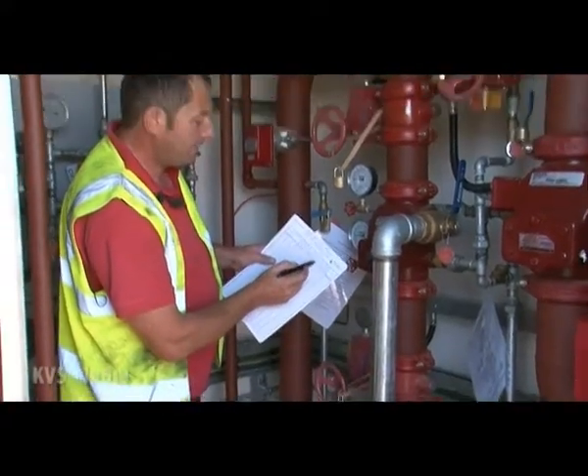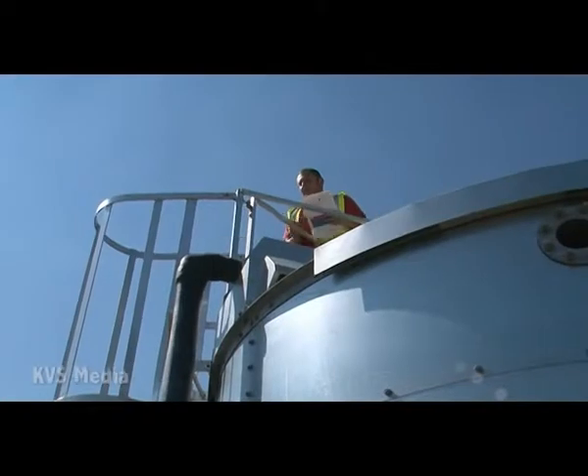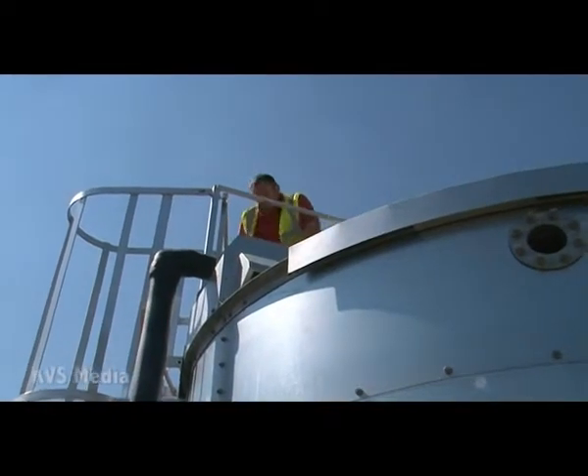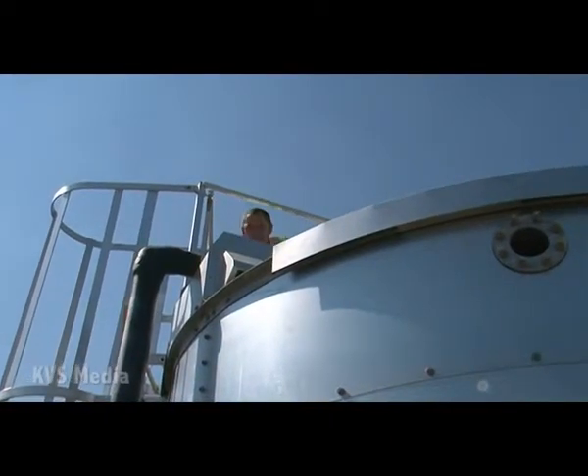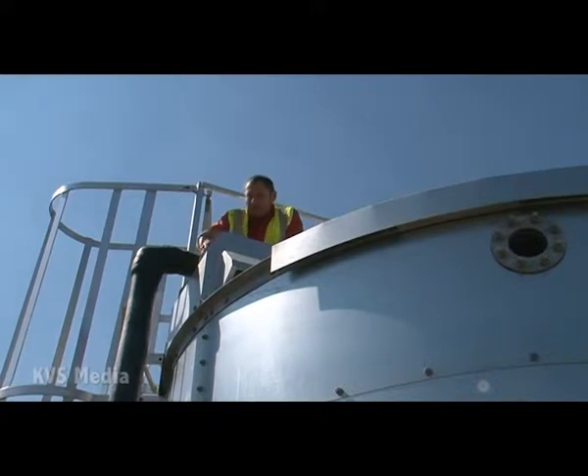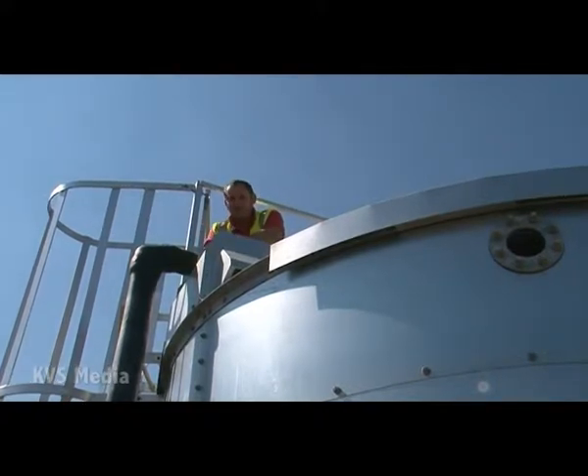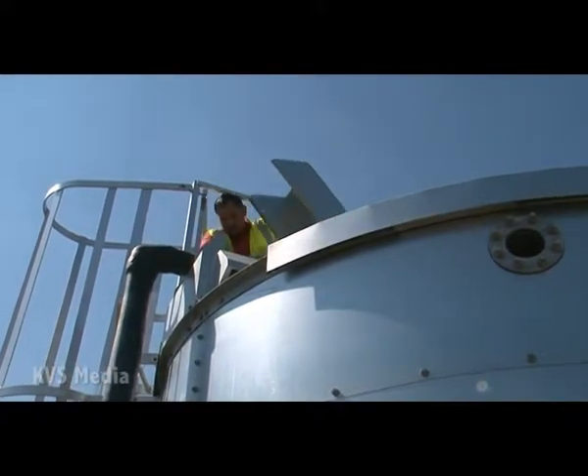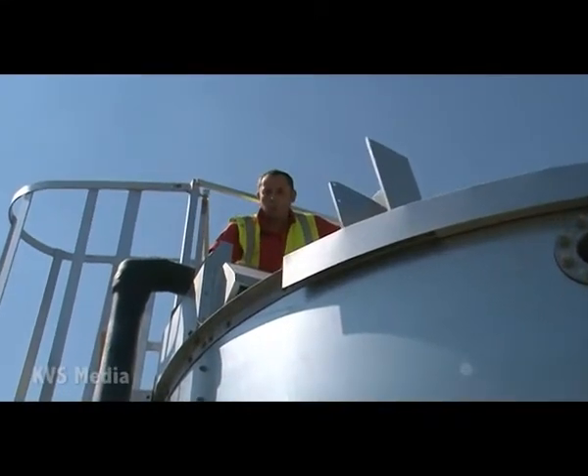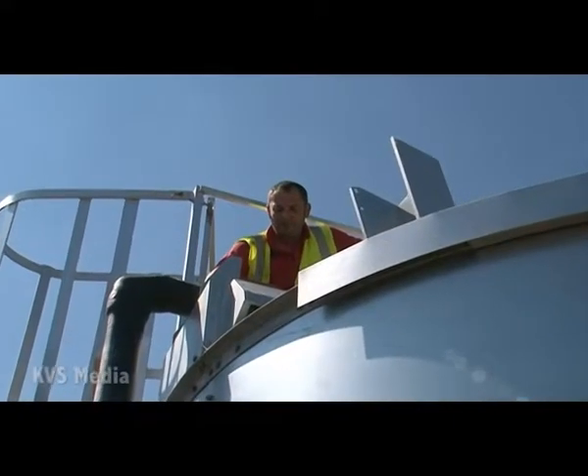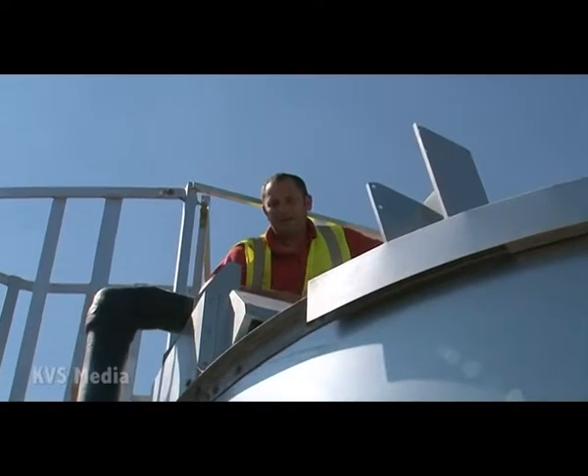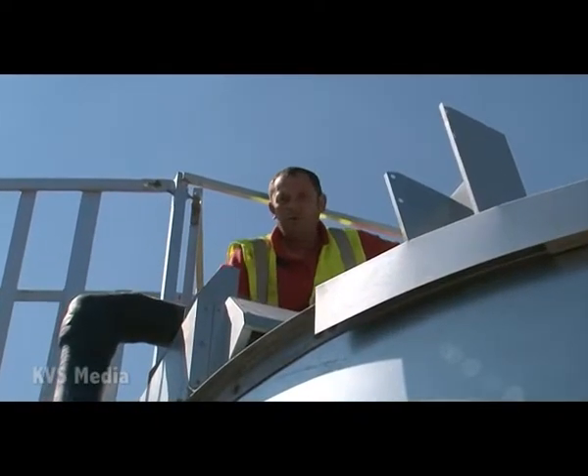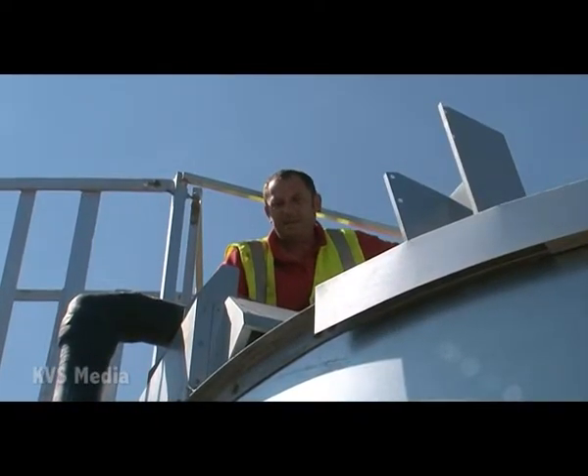water storage tank full, and physically open the hatch and check the water level is full. We have just done the weekly test, so therefore water is seeping back into the tank. This will stop once water level has reached its full mark.